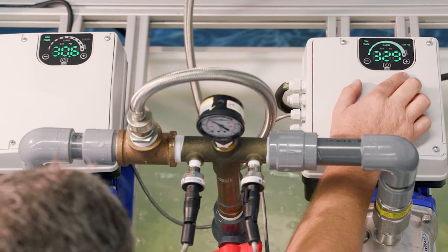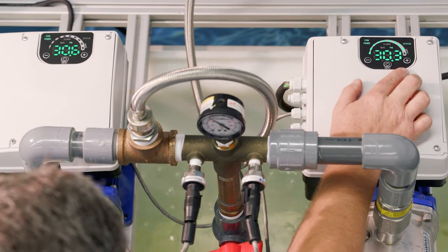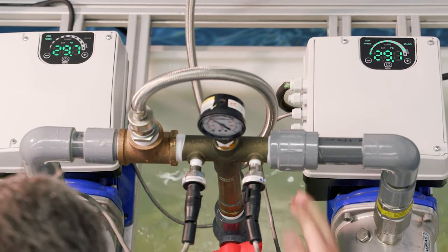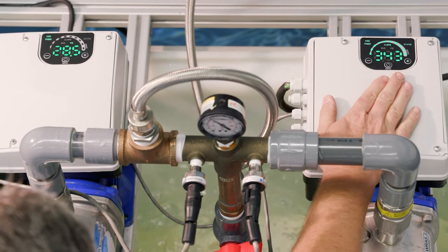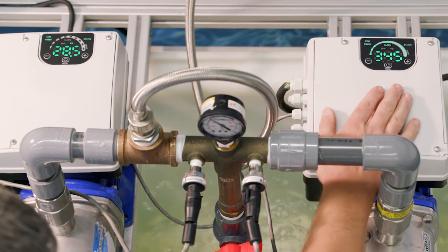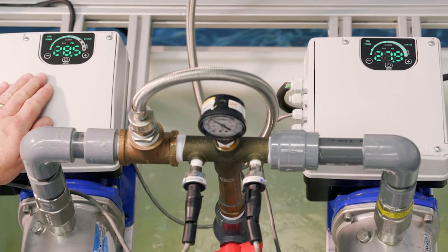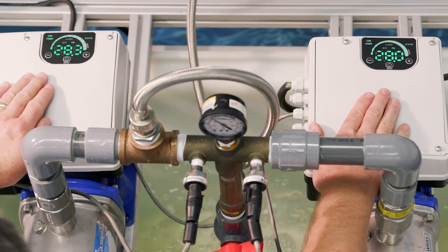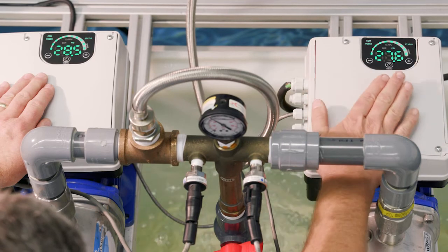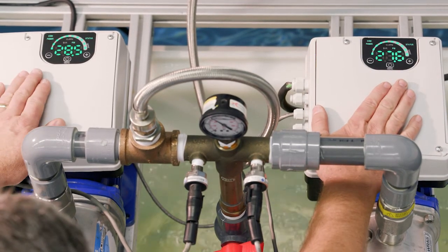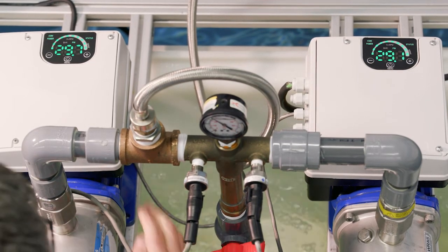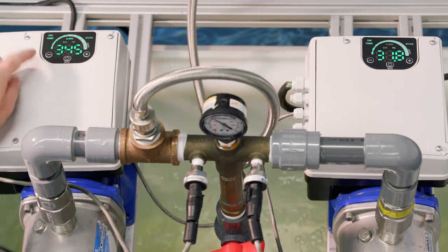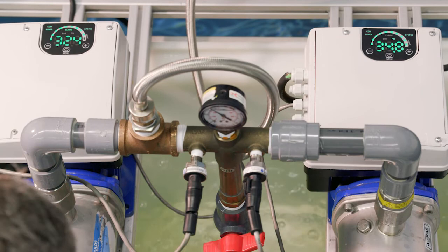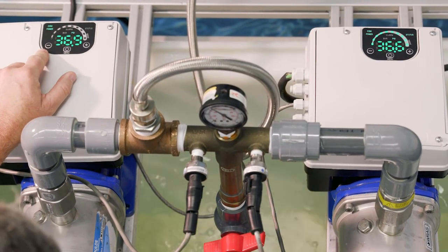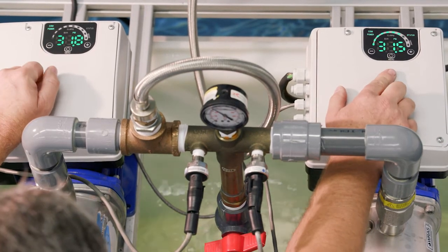Climbing, you can see the speed is increasing. Still seems to be keeping up with demand. Add a little bit more demand. So looks like we're at full speed over here. Unable to keep up with the demand. So now it turns the lag pump on. So let's see if we can dial it down to show you. In serial cascade, we always have the lead at full speed, and then the lag is the one that's going to vary. So we'll change to show you speed again here. So we can see the speed going down, right, while one was maintaining that speed.